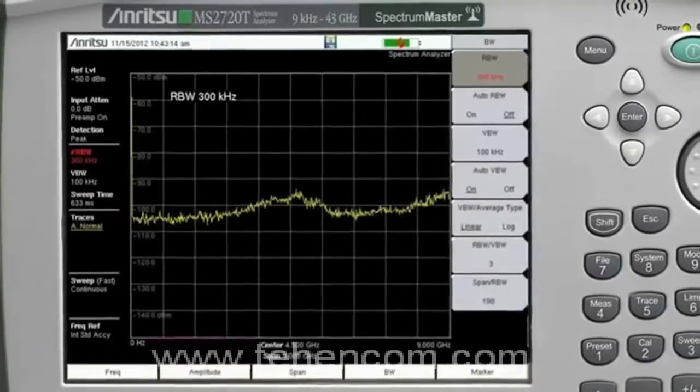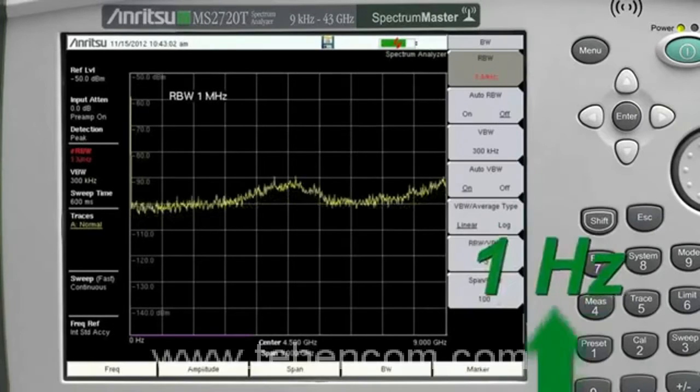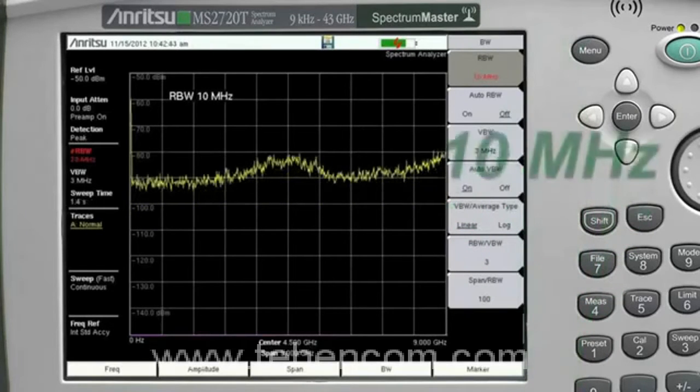Resolution bandwidth and video bandwidth choices go from 1 Hz to 10 MHz, giving you the freedom to choose the sensitivity of the instrument. With the new digital IF, you can have good sensitivity without sacrificing sweep speed.